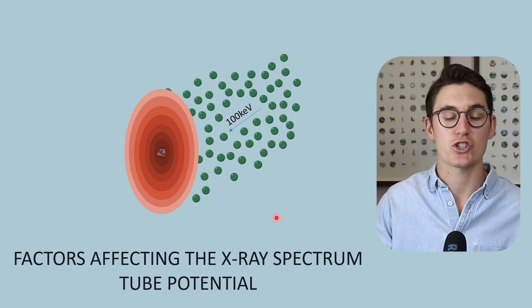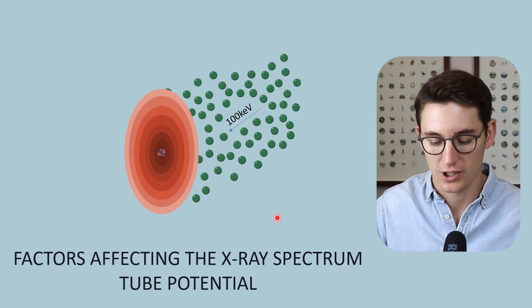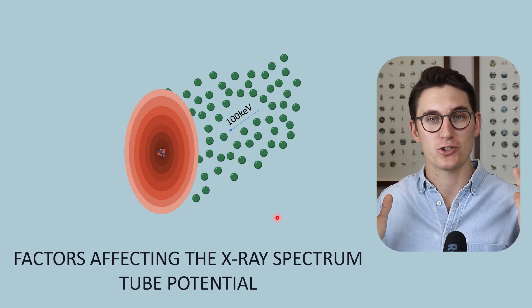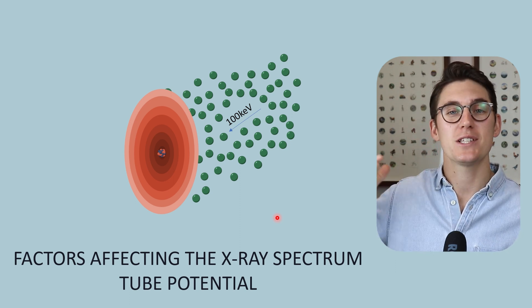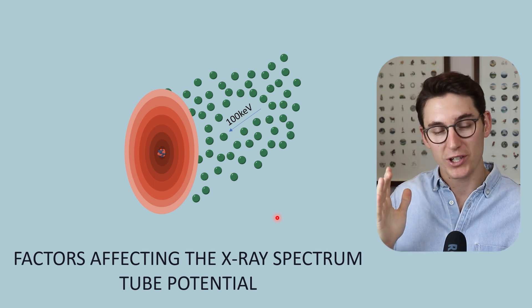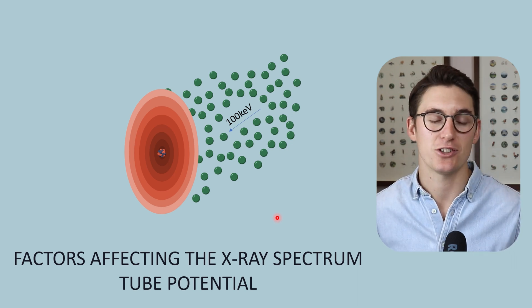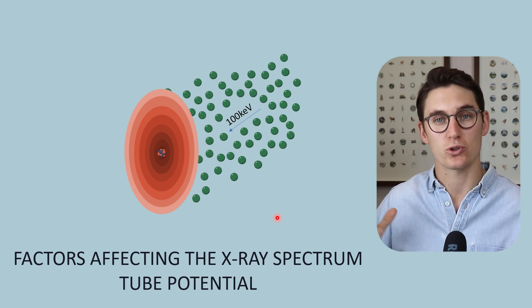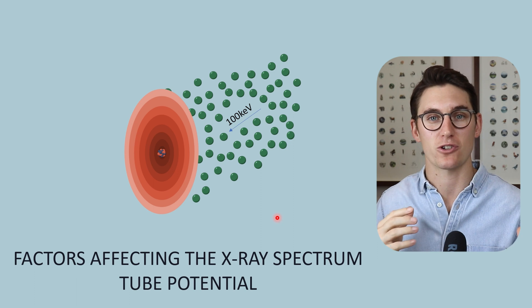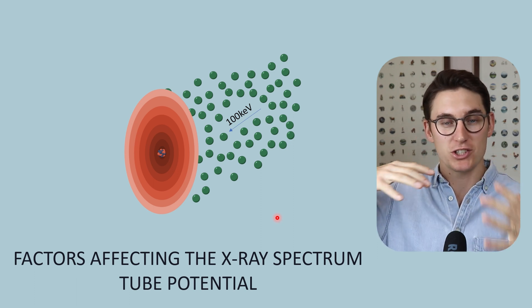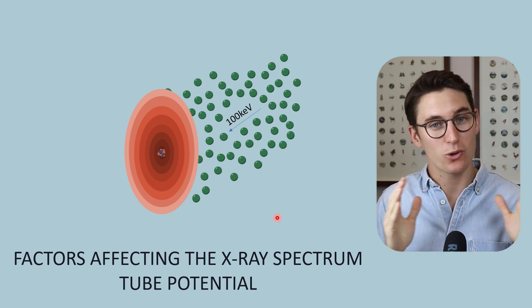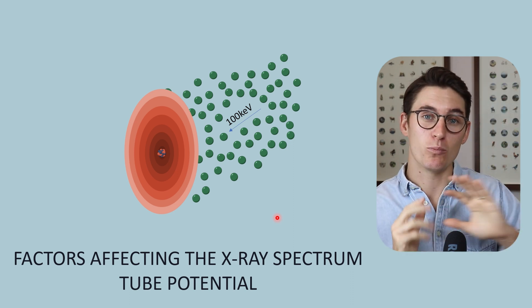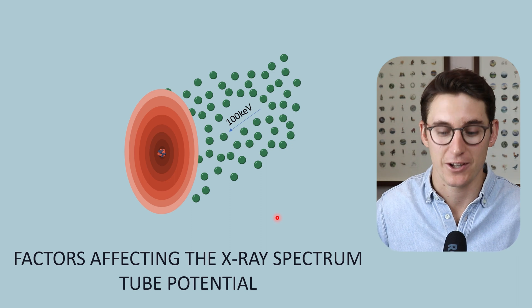The second thing we can change is our tube potential. Our tube potential is what accelerates electrons from our cathode to our anode. So increasing our tube potential will increase the energy of those electrons heading towards our anode. Not only does it increase the energy of those electrons, but it also increases the number of electrons on the surface of that filament — as we increase our tube potential, we pull more of those electrons away and send more towards our anode.